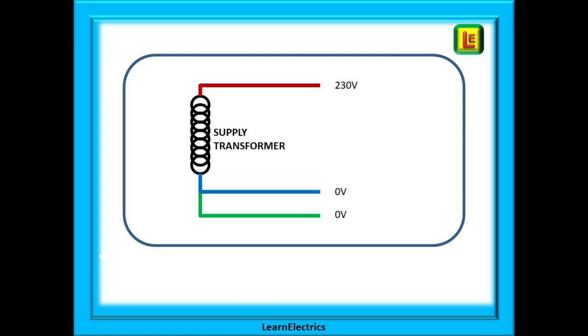The supply transformer in this case gives us 230 volts on the switch. This will make sense as we build up the picture. With a switch in the closed or on position, voltage 230 volts can pass through the circuit. Open the switch and 0 volts enters the property. But be aware that 230 volts is still present on the supply side of the switch. It is only the output side that is zero.